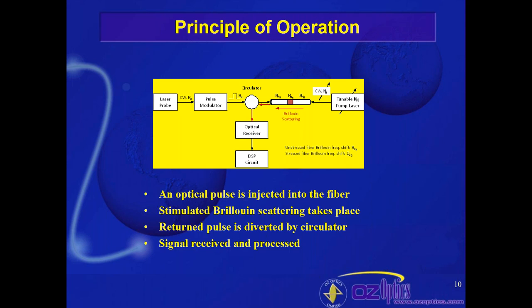We can improve signal strength by adding an additional pump laser at the opposite end of the fiber going in the opposite direction. This acts as an amplifier for the signals we're measuring, because the return signals are very weak — on the order of nanowatts and picowatts of energy. The pump laser amplifies the return signal so we can achieve better resolution and precision.